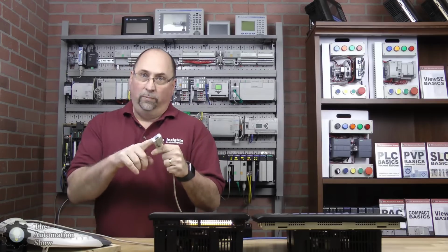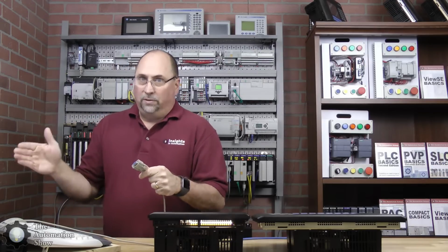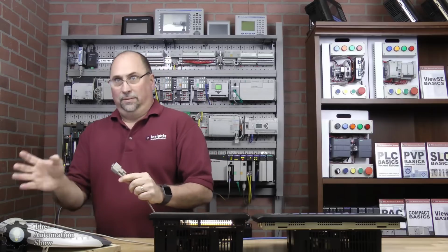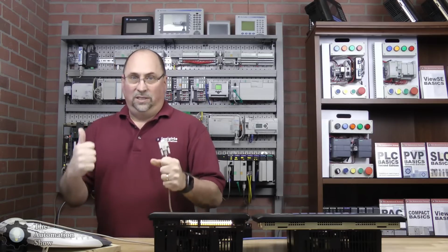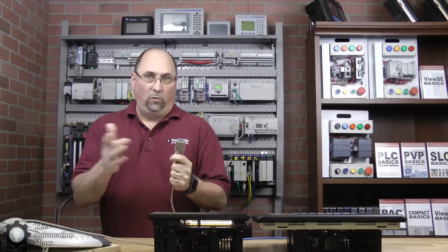This is not a null modem. This is straight through. When you go Allen Bradley PLC to PC, both devices are DTEs, okay? So you need a null modem or crossover cable.